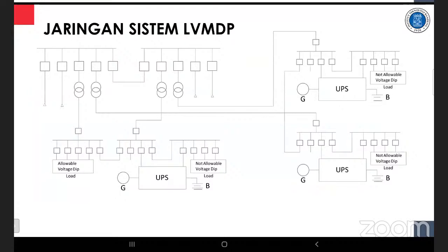For the low voltage, we have added some UPS and other points to get better reliability without voltage dip. We calculate all of the load, separating loads that are not allowable for dip and loads with allowable voltage dip. We cluster these and add the UPS system there.